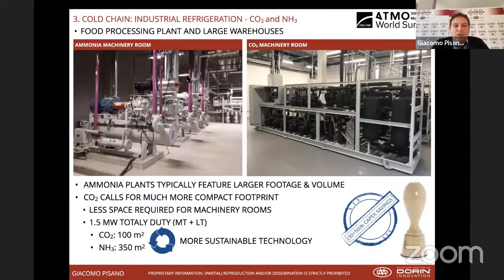When it comes to machinery room, CO2 is also able to provide a much more compact environment where you can install your racks. On the left side, you see an ammonia machinery room. On the right side, you see a CO2 machinery room. Clearly, CO2 brings in a much lower footage needed. For a 1.5 megawatt total duty, you can assume you will need about 100 square meters for a CO2 rack and 350 square meters for an ammonia rack.